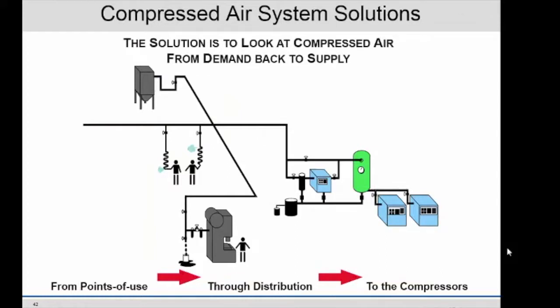Compressed air. In fact, there's a session going on in parallel with this on compressed air. It's really big energy savings. We do a lot of compressed air projects. These compressed air systems are just so simple, so archaic, that they just waste a lot of energy. They just cycle the air, 125 to 100 and back and forth, and dump any air they don't use in the system, because it's a centrifugal air compressor and you can't back off the airflow on a centrifugal. So it dumps all the air in the alley that you're not using.